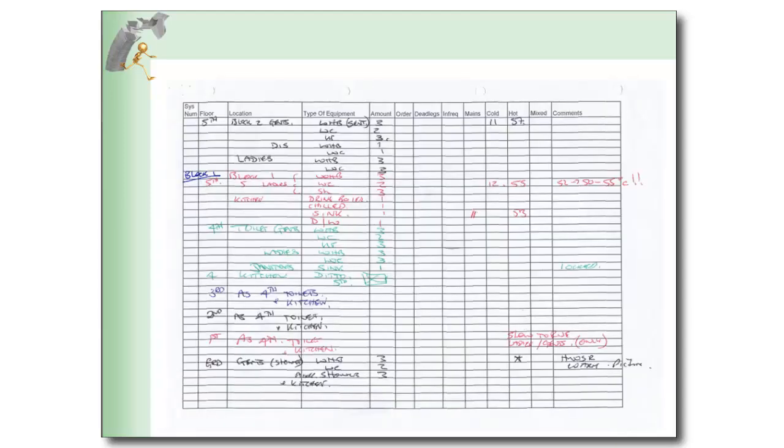I usually do a little sketch like is in front, and I know whether it's got a lid by my drawing, whether it's got a hatch, whether it's got screened overflows or not, whether the inlet and outlet are in the right place. I actually only have to take a very small number of notes to be pretty sure that I've got all the records I need. I haven't been able to find a piece of software which comes anywhere close to the speed that you can get a report down on a piece of paper. So we don't actually utilize software for collection.